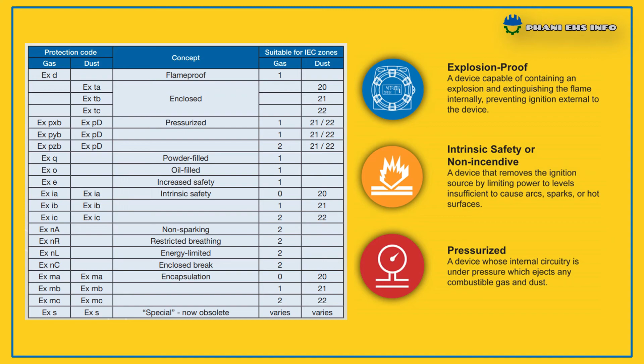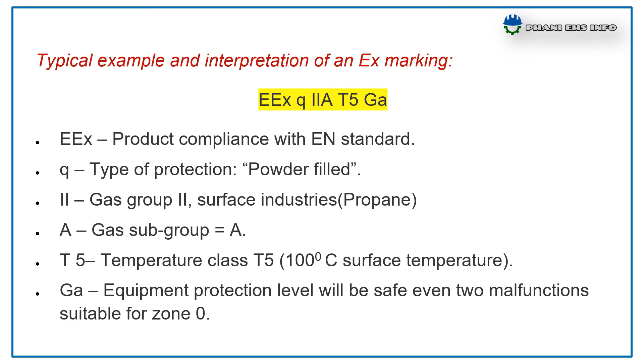The example of explosion classification, here we see EEx, this is product compliance with EN standards. Q, the protection concept is powder filled. 2A, suitable for use with gas group 2A, which means propane. T5, maximum surface temperature 100 degrees Celsius. Ga, very high equipment protection level, will be safe even after 2 malfunctions, suitable for zero zone.